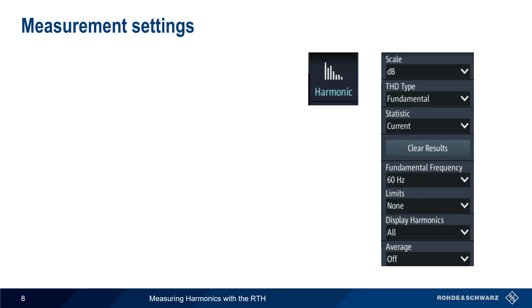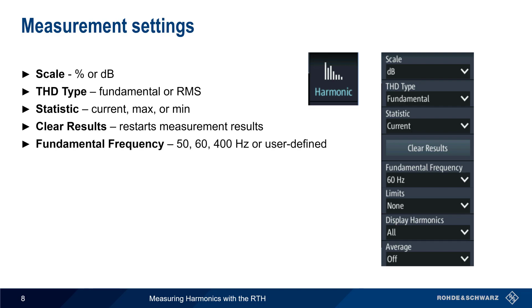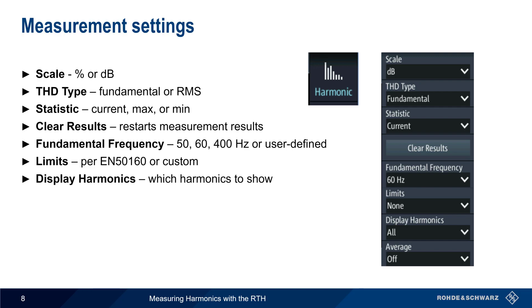There are a number of different measurement settings that are used when measuring harmonics. These include the measurement scale, the method used in computing total harmonic distortion, and the type of value shown — current, max, or min. The clear results button can be used to reset these statistics. Although the RTH can usually automatically determine the fundamental frequency, this can also be manually configured. Limit testing as per EN50160, or a user-defined set of values, is also supported. The number and type of harmonics to display is user configurable as well. Finally, results can be averaged to reduce the effects of random variation in the measurements.